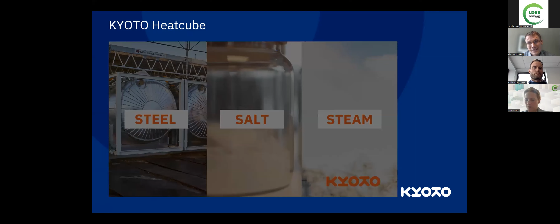Here is a little bit about the key features of our system. As said before, charging capacity can be scaled to the need of the customer, 10, 20, or 30 megawatt electrical. That then goes into thermal. The storage capacity depends on how many tanks you put together, so between 16 and 96 megawatt hours. Discharge capacity is up to 5 megawatt. With discharge in the form of steam, it can be both superheated and saturated steam, and the temperature range of our steam is between 170 to 400 degrees. Our salt temperature is 115 degrees, and the footprint is around 250 square meters, up to 310. The height is approximately 8 meters, and the weight is between 400 to 1,500 metric tons.